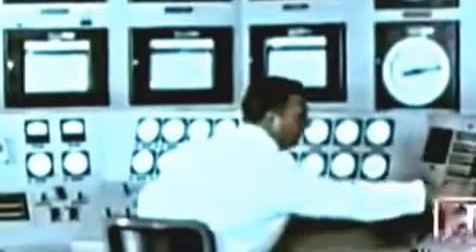On July 26, 1959, technicians barely managed to manually shut down the sodium reactor when temperature and radiation readings quickly jumped. Then, after 2 hours of basic inspections, they made a baffling decision. They started up the reactor anyway. They operated the reactor for about 2 more weeks before the radiation levels rose, and there were so many signs of trouble that they thought it was time to stop and to get real serious about finding out what was going wrong.